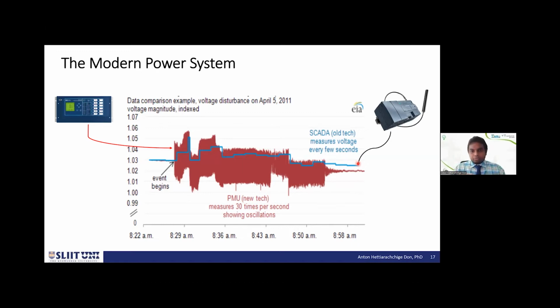The visual improvement you see here is the refresh rate, how often we get a new data point. PMUs, the new technology, measure about 30 times a second. This graph is a little older; right now we have PMUs that do 60 and even 120 times a second. That means several times within a power cycle. If you have a 50 or 60 hertz system, it takes measurements several times per power cycle, whereas the old SCADA system only updates every few seconds, so you miss some events. That is the major benefit PMUs give us.